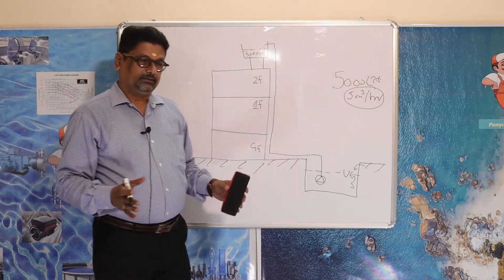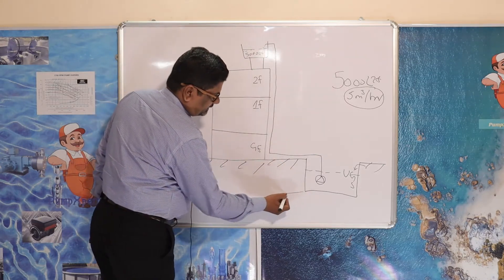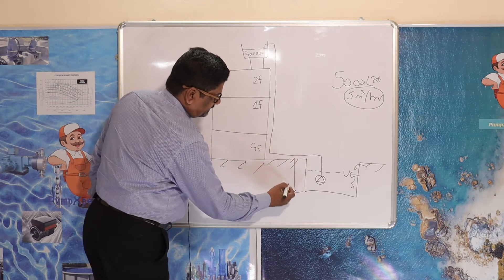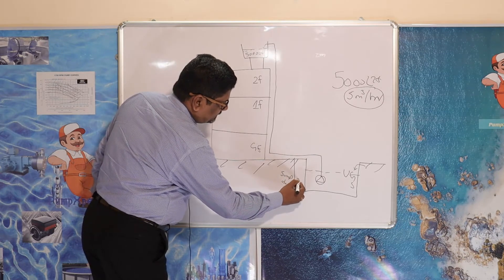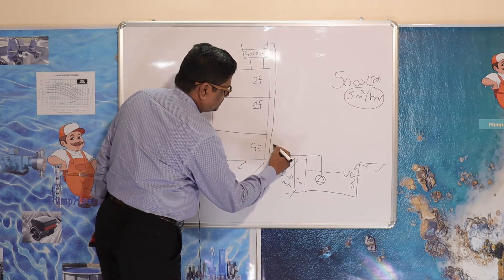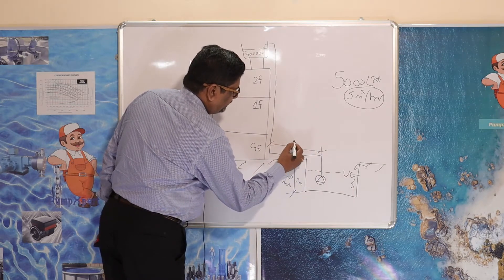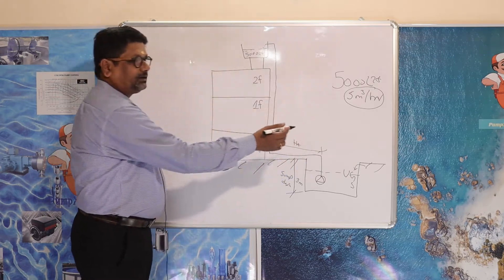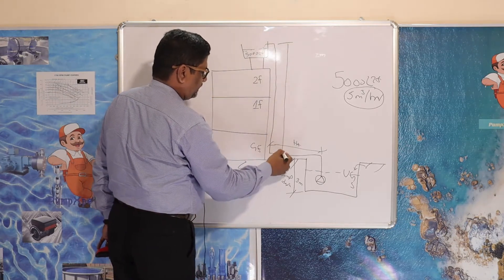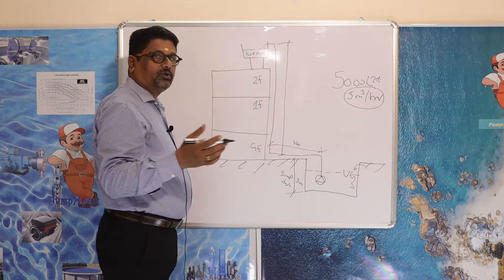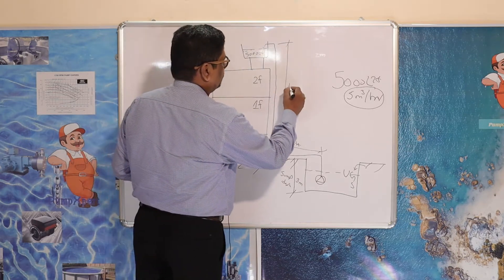Now I have the flow. I need to know the head. Head is simply the distance from the sump to the tank. The sump depth — let's call it A — I will put as 3 metres. Then there is the horizontal distance, where you take only the friction head on the horizontal line. Then there is the vertical height of the building along with the tank — since it is 2 floors plus a third floor with the tank, I assume it is about 12 metres.